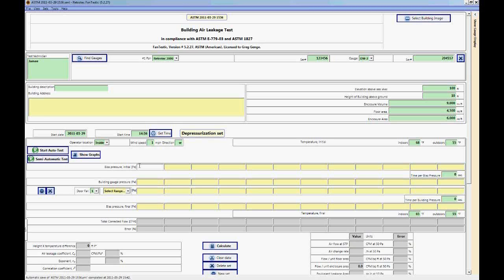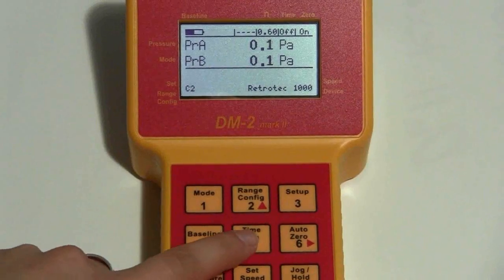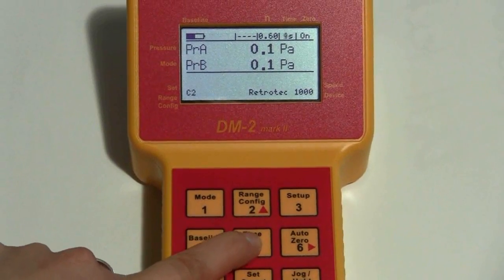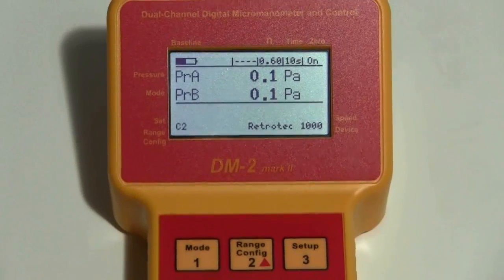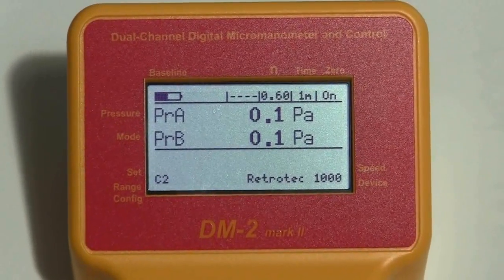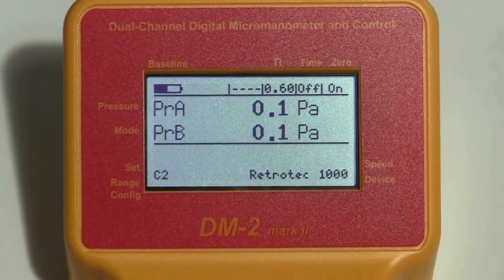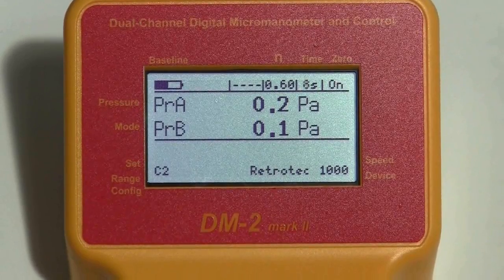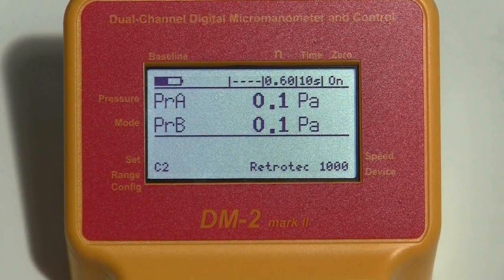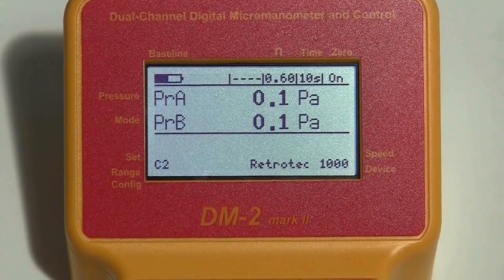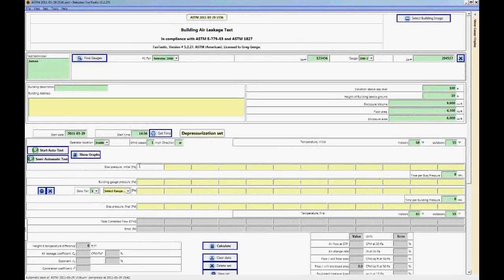All you have to do for that is to push the button that says Time Avg and that's number 5. And the more you push it the higher the time average is going to go. So we've got 1 second, 2 seconds, 8, 10, 20 seconds and then it goes up to 1 minute. So if it's very windy we recommend taking longer bias pressures. If it's not so windy then you can get away with taking a bias pressure of 10 seconds which is what ASTM recommends.